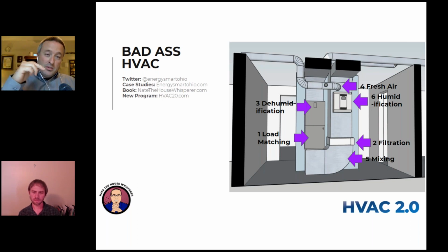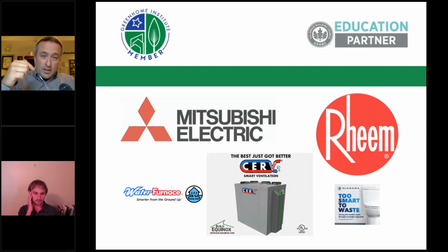But again, if it's humid outside, not everyone understands, like an ERV, yes, it will reduce the humidity of the air coming in to some degree, but it's still adding. So instead of bringing in 100% of the outdoor humidity, maybe it brings in 50%. But if you're bringing in a large volume of outdoor air, you have to dry that air, or else you're going to cause other problems. So very high flow rates in humid climates can be very challenging. So you're saying when you make it a separate system, you're creating a humidity issue.